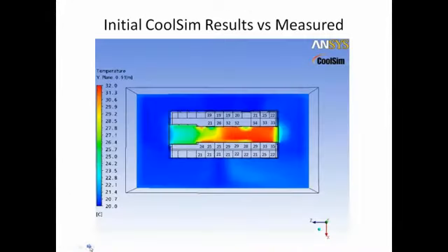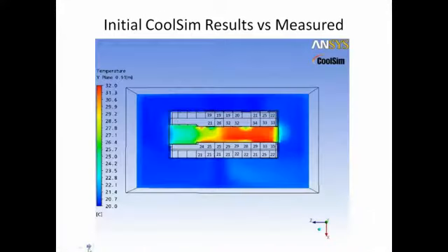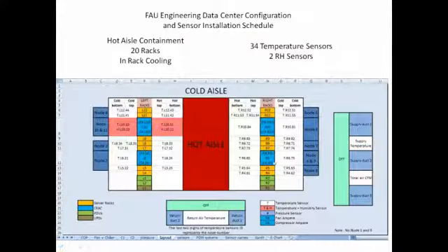Okay. By the way, one more thing. Can you just go back? Yep. The CRACs are actually in line here, so the blue areas are indicative of where the CRACs are. And they're APC in-row units, I believe, right? Right. You can see we've got a fan input and a compressor input there. Those are actually sensors that were already installed that we've just picked up.